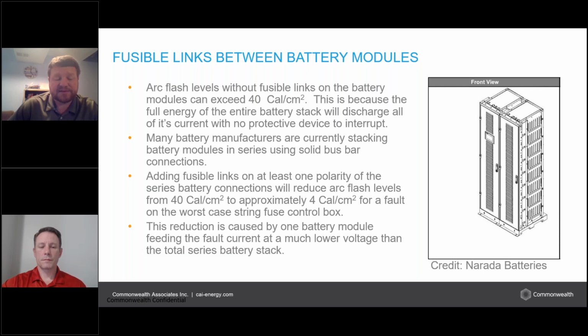And the other concern with working with batteries is if you have the doors on the outside, at least you have the ability to escape. But if you're working inside these containers, the idea that you can escape a fault within 2 seconds may not be actually reasonable and possible. So if that's the application where you're inside the container and there's not a clear and easy escape route, then it's much more important to be thinking about this.